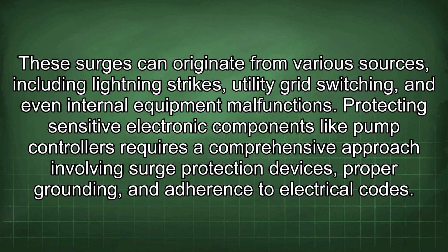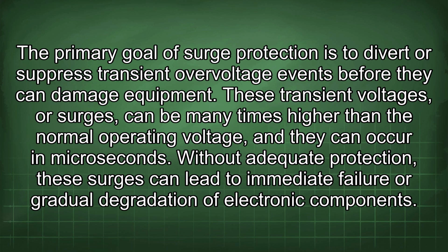The primary goal of surge protection is to divert or suppress transient overvoltage events before they can damage equipment. These transient voltages, or surges, can be many times higher than the normal operating voltage, and they can occur in microseconds. Without adequate protection, these surges can lead to immediate failure or gradual degradation of electronic components.